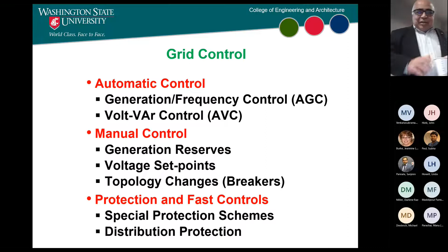So what are the challenges here? The big problem with automatic AGC is that instead of having to ping 10 or 20 generators to keep up with the load, now you might have to do 100 or 1,000 generators. And that requires you to divide up these controls further and further as you go down to the lower levels of generation.